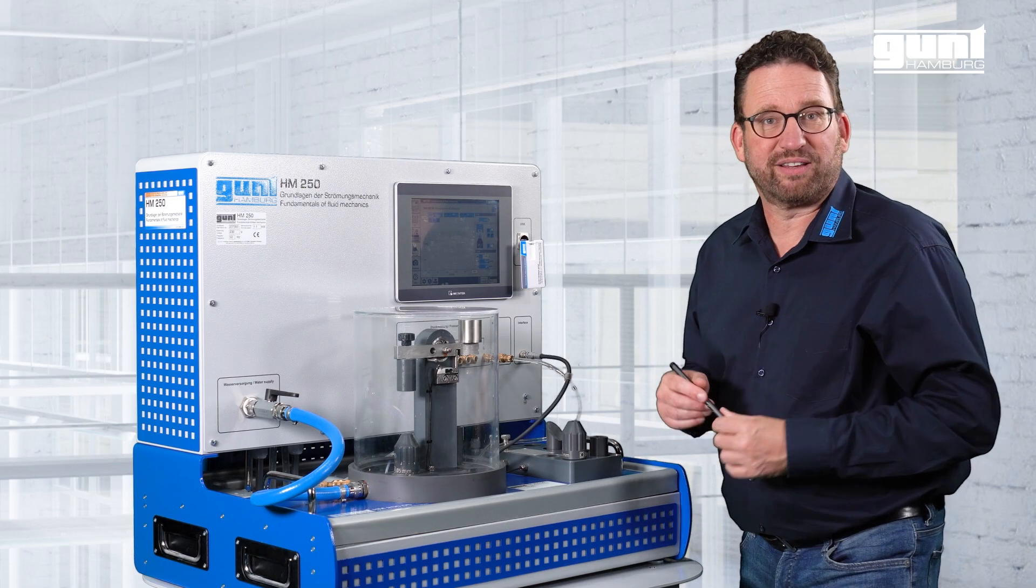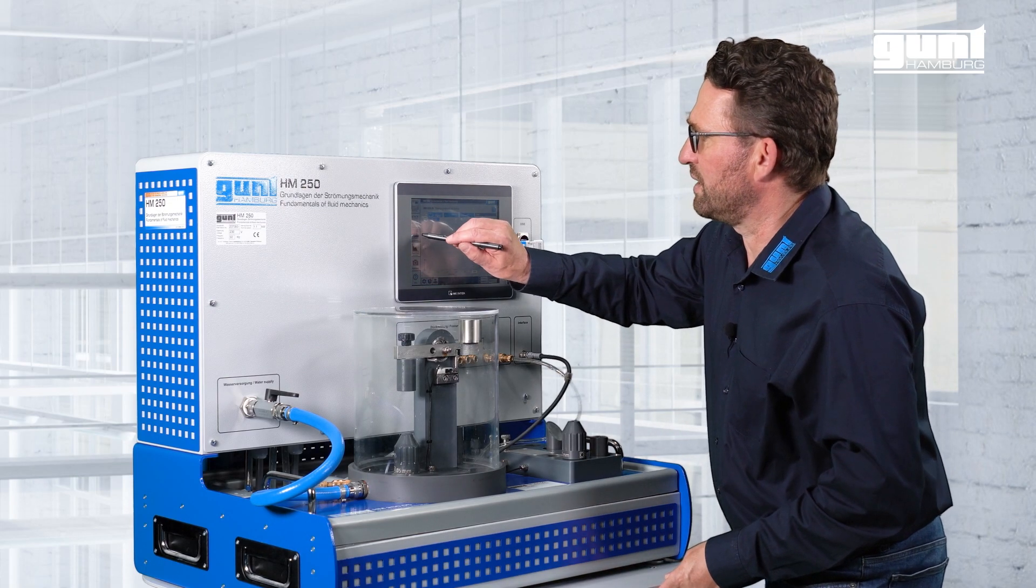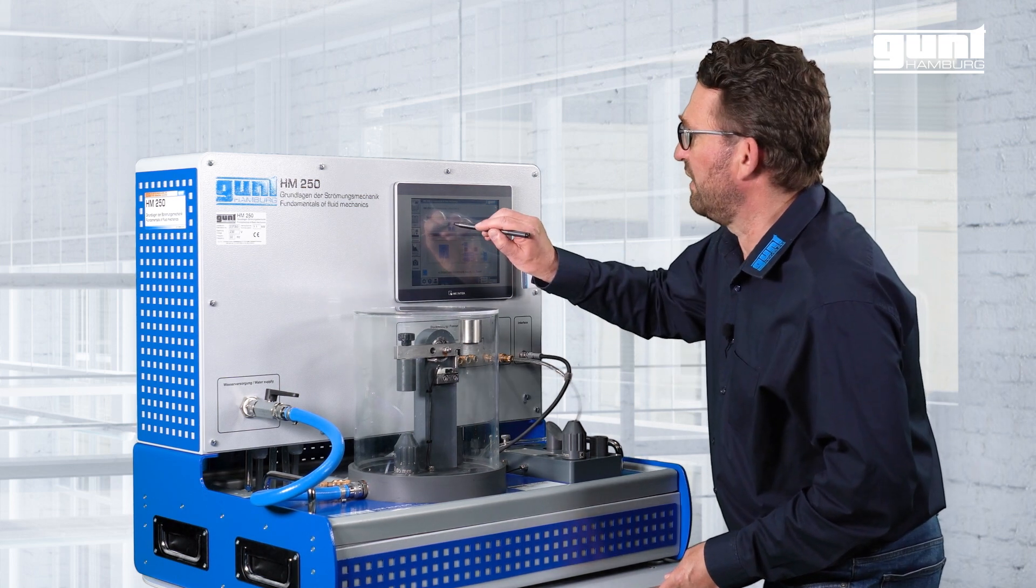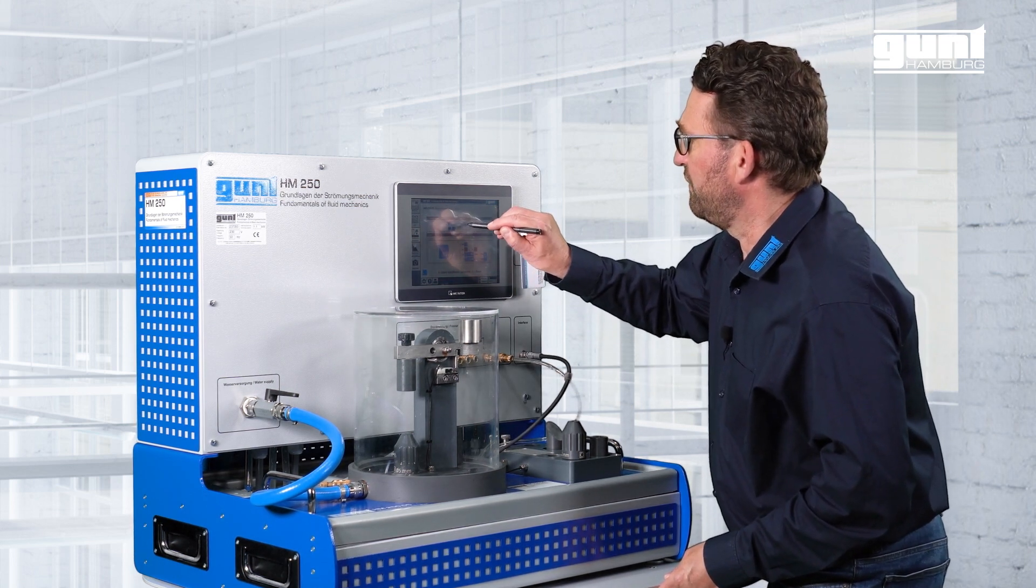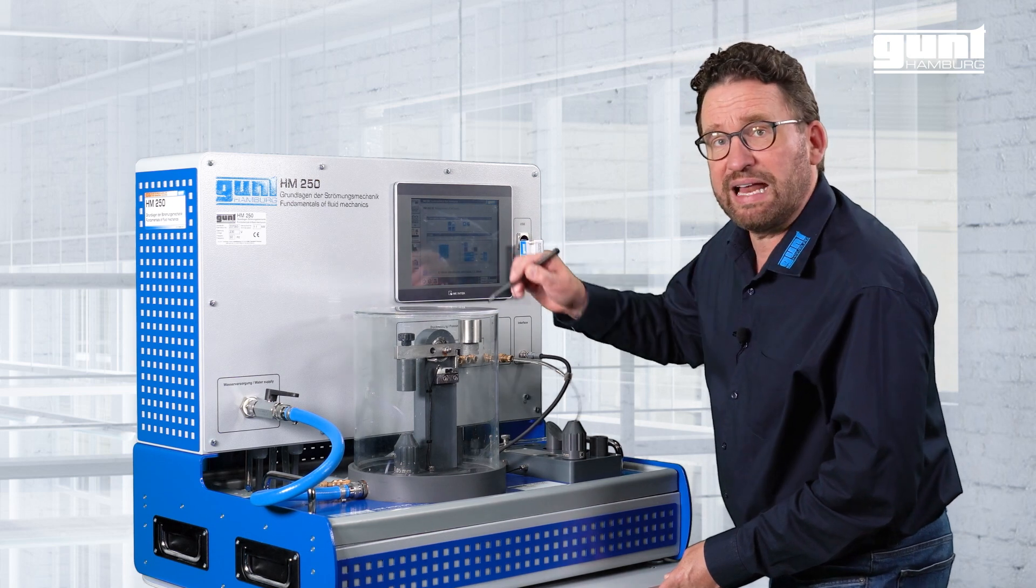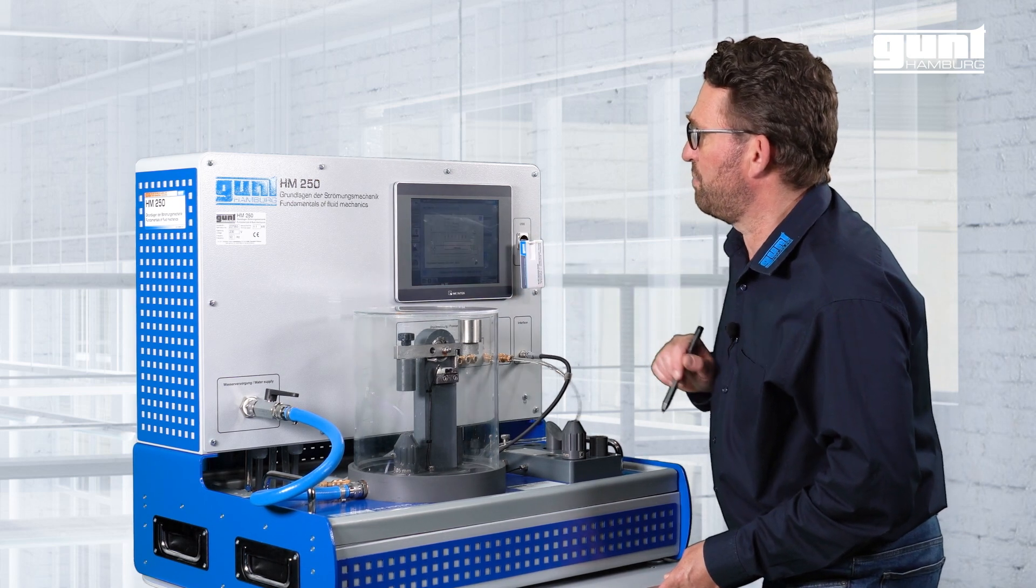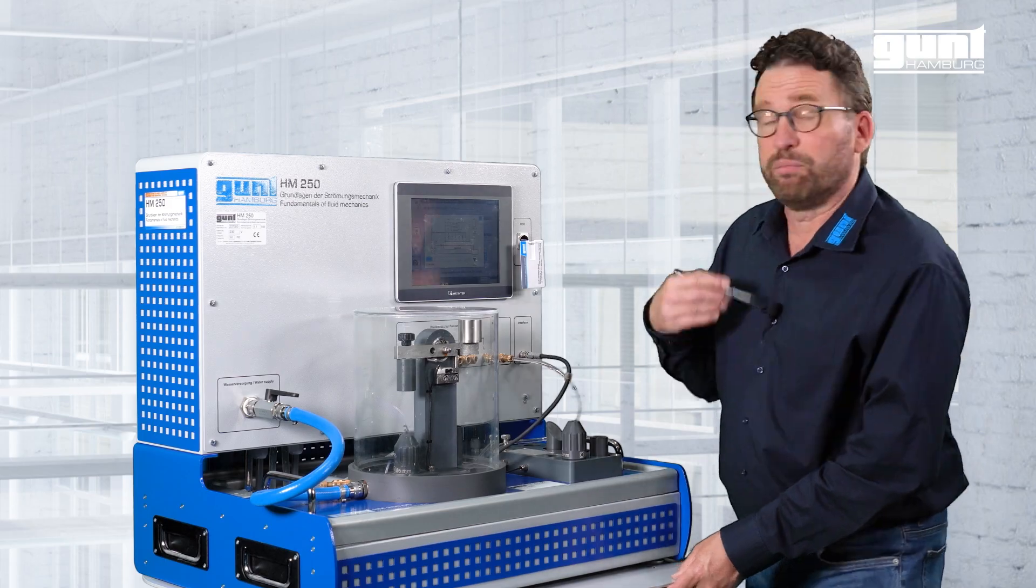In order to start the experiment we change into the experiment preparation screen where we select the appropriate deflector and nozzle size and after that we start the bleeding by pressing this button. The bleeding process is carried out fully automatically by the unit.